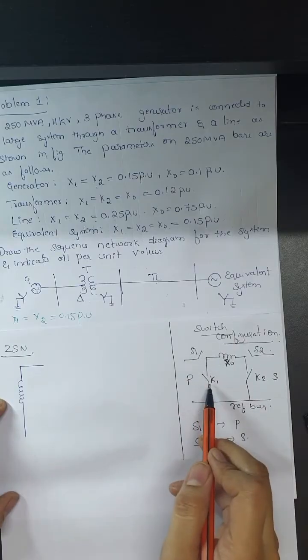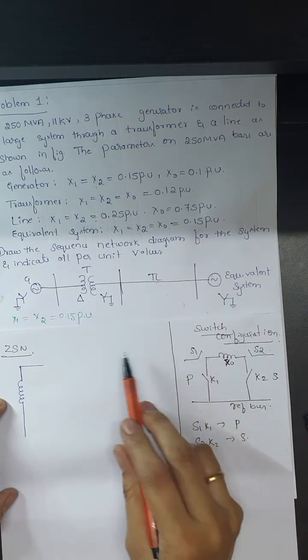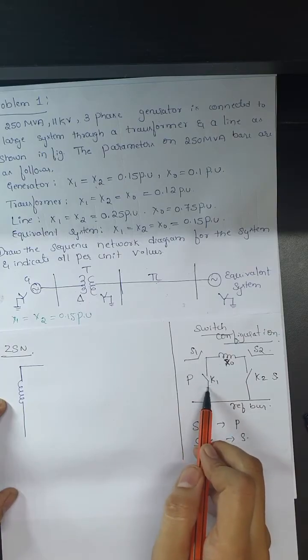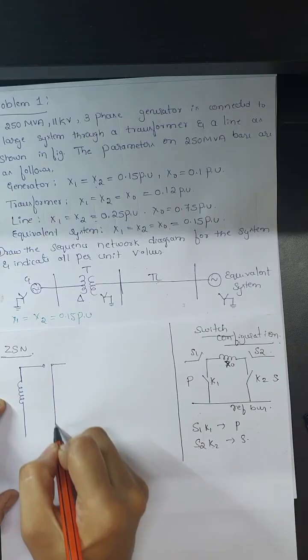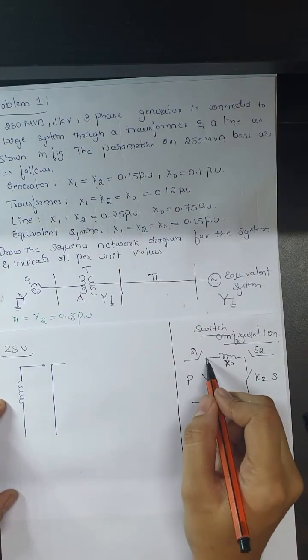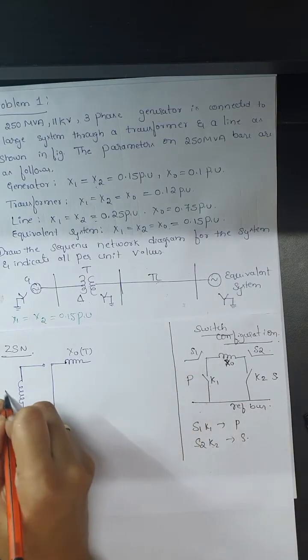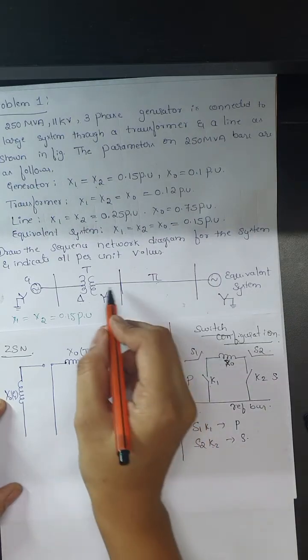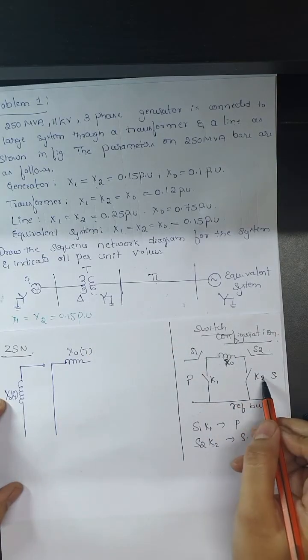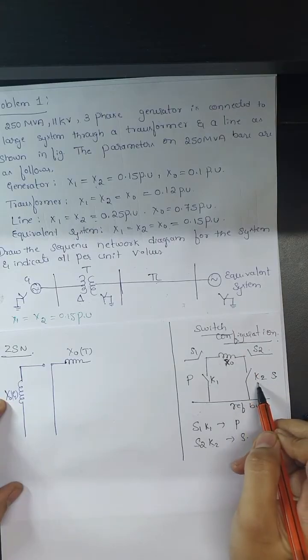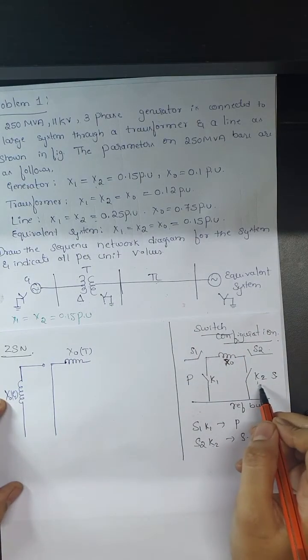Since the primary side is delta: K1 should be closed and S1 should be open. With K1 closed, the next connected component is the reactance X0 of the transformer. For the secondary side, which is star connected with neutral solidly grounded: K2 should be open (no delta), and S2 should be closed since the neutral is solidly grounded.